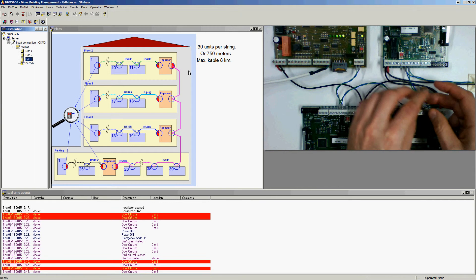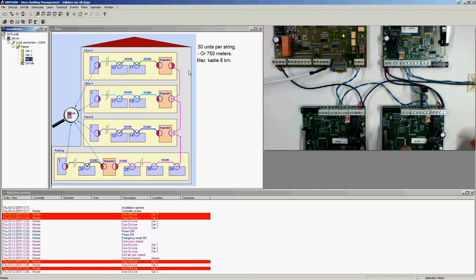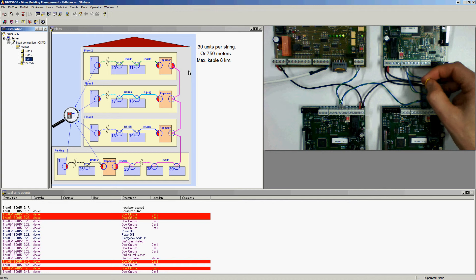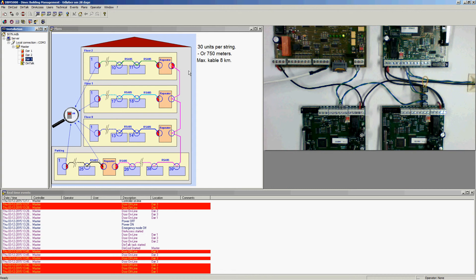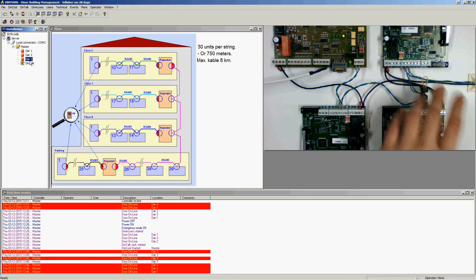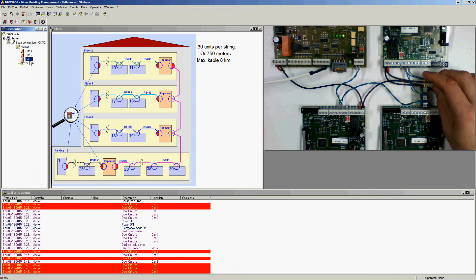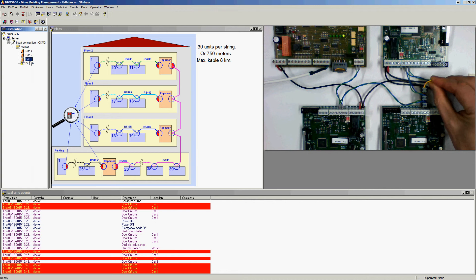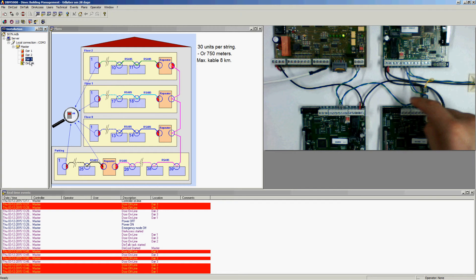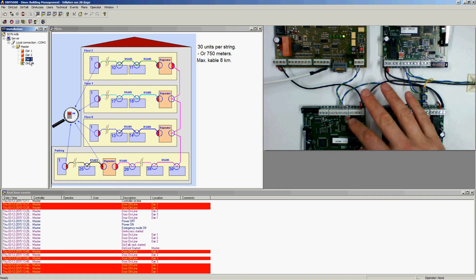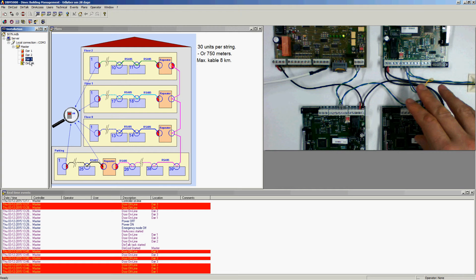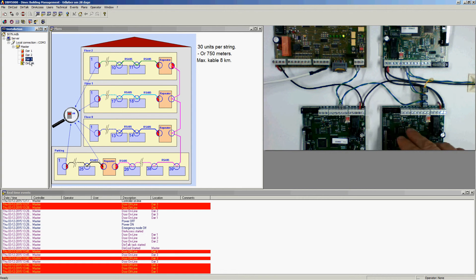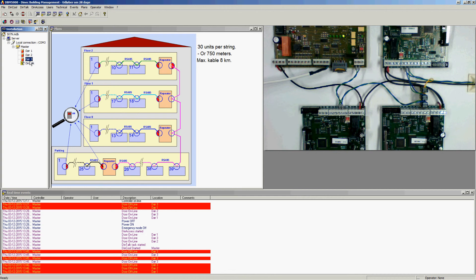But if something else is happening on the bus, it could be that this small chip we have here would be short-circuiting because of lightning. If that happens, we immediately see no communication to any of the doors. If this were a larger installation with a lot of meters of cable, it could be a remote door — say 100 meters out — with a short circuit on the line. Because of the cable length, we might still have contact to some of the doors nearby. So you can't really tell which doors would acknowledge the signal from the controller. It's very random, so you have to make a decision about what to dismantle.